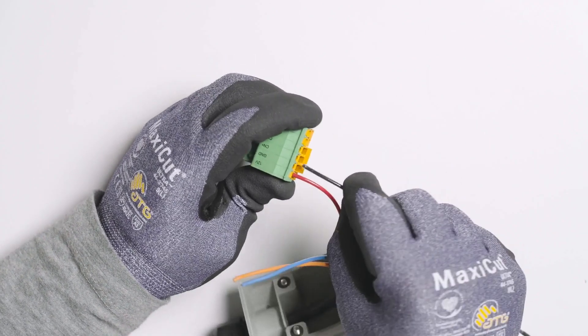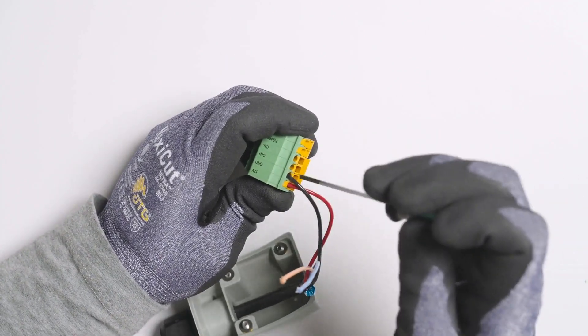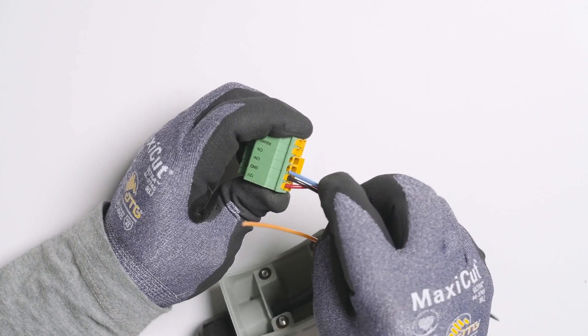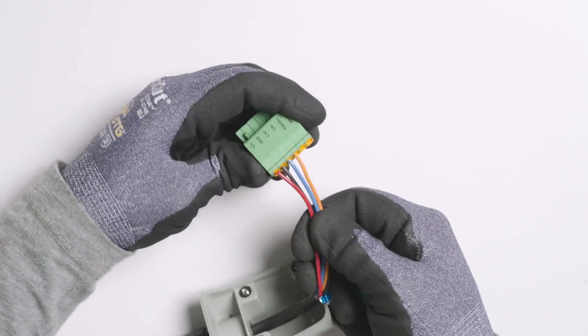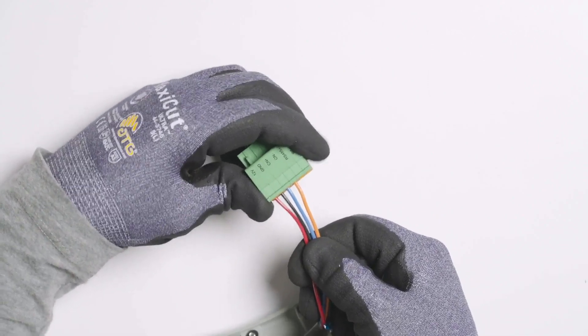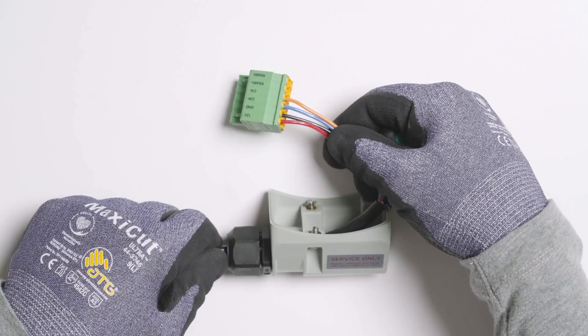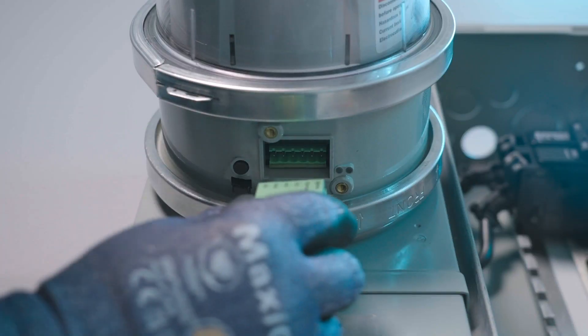Use a screwdriver to close the orange tab. As the orange tab is closed, the insulation around each wire is pierced, making an electrical connection to the terminal. Perform a slight tug test on each conductor to ensure that they are fully seated in the terminals. Once all four conductors are terminated and tug tested, plug the connector into the bottom of Backup Switch.